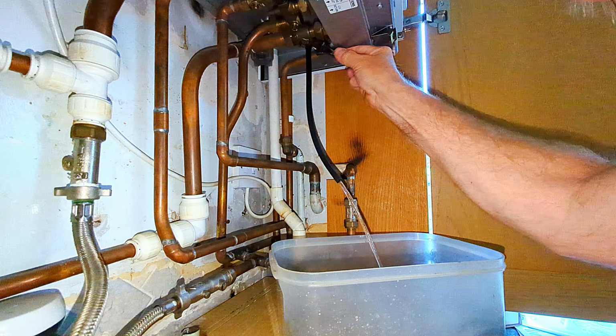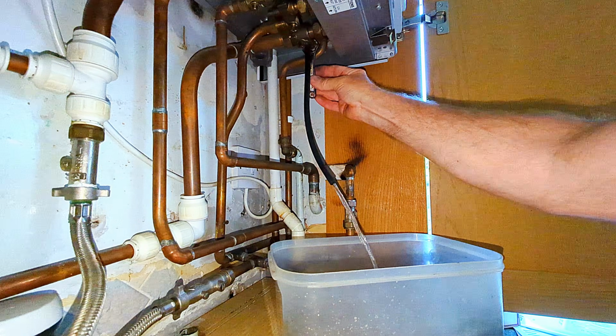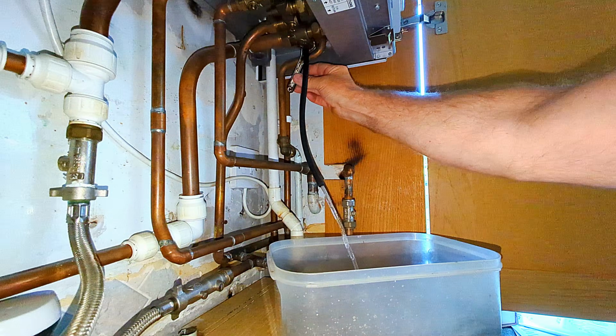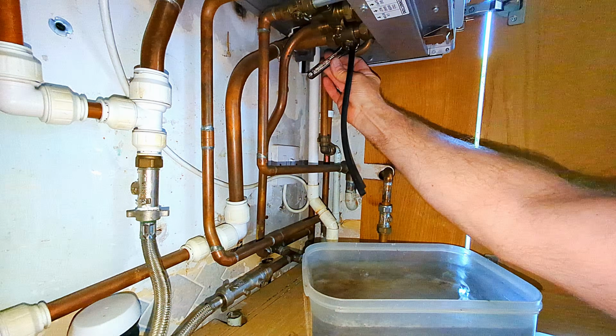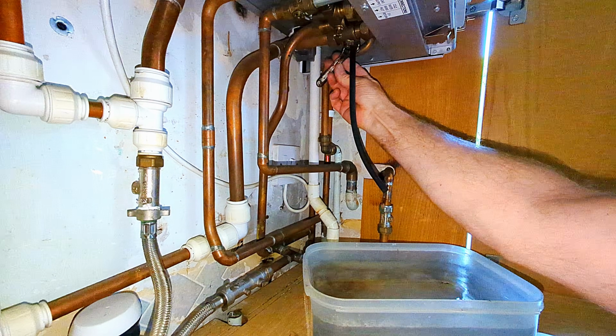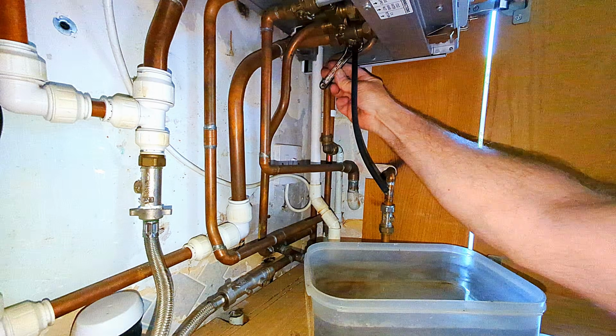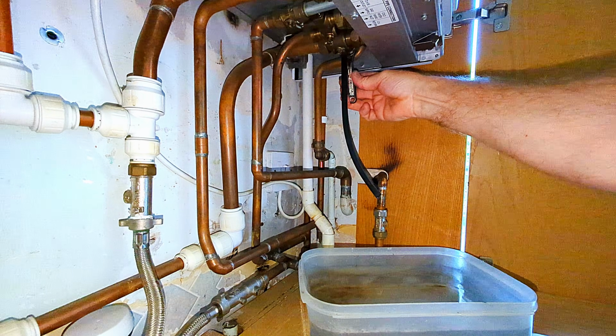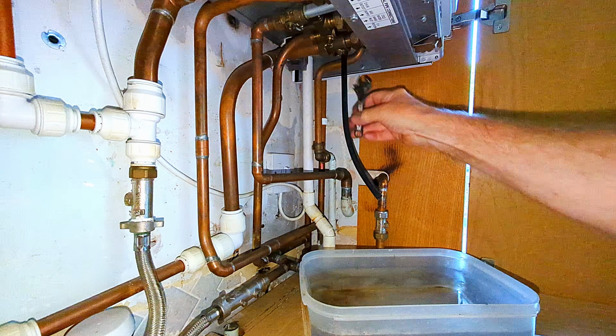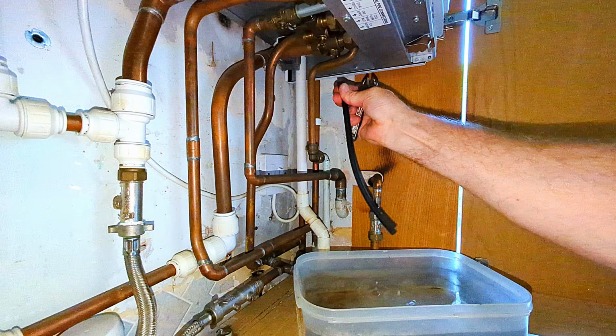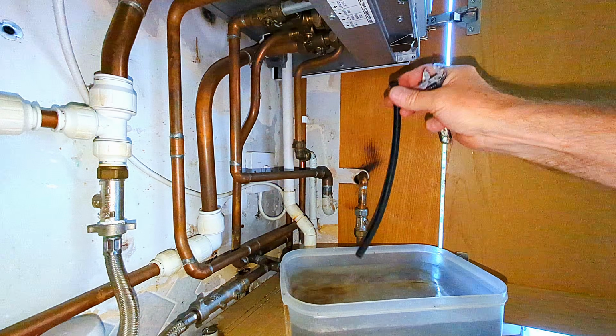After the water has stopped coming out of the drain valve and the pressure is down to 0, I'm then going to close that drain valve back up again, because as soon as I remove the pressure sensor, that will break the airlock and I'll get water pouring out of that drain valve. And there we go, my boiler is now all drained down and I'm ready to replace the pressure sensor.